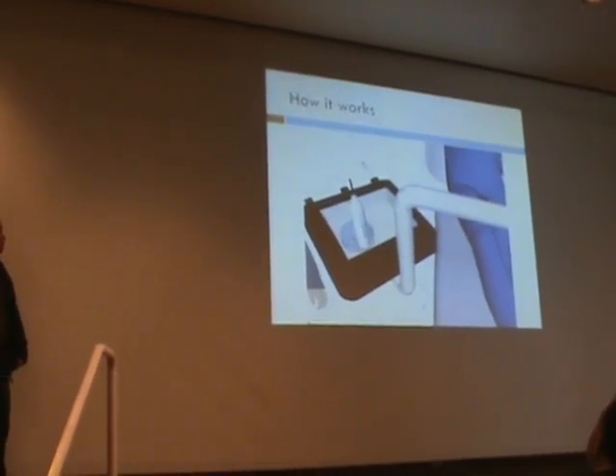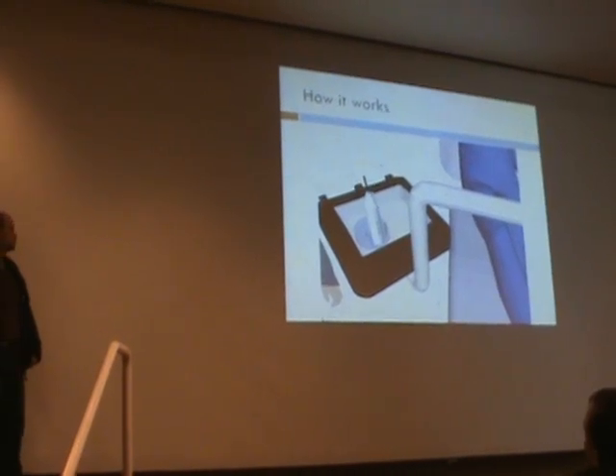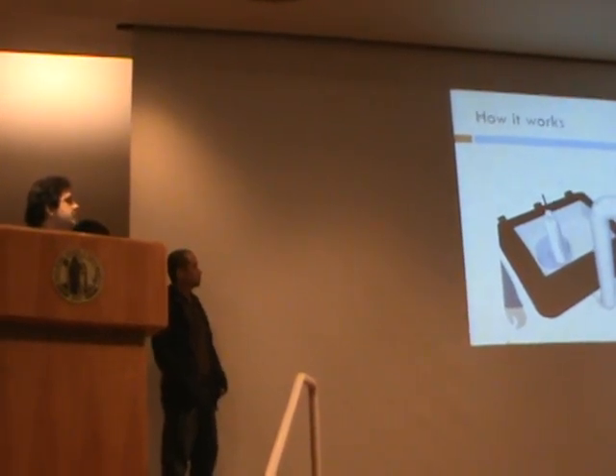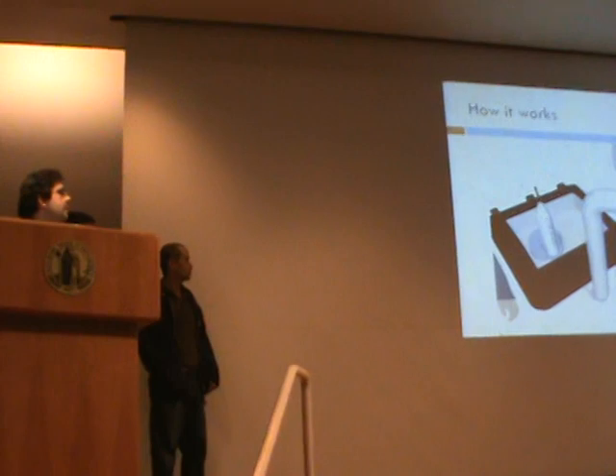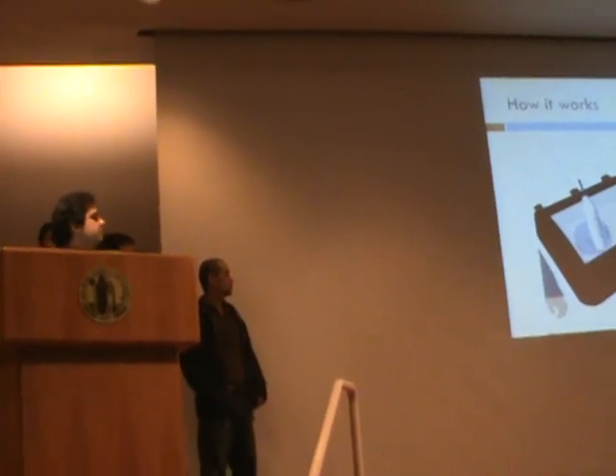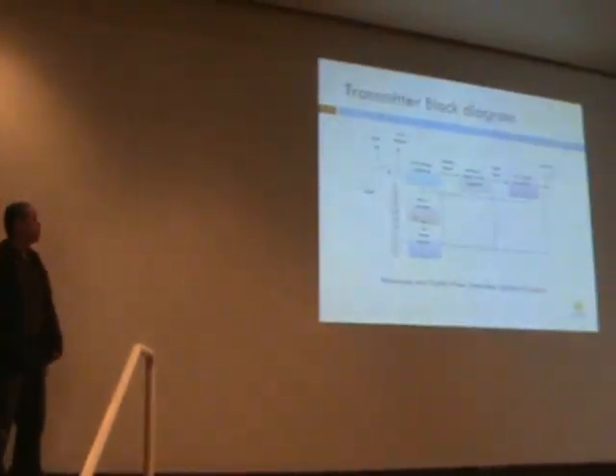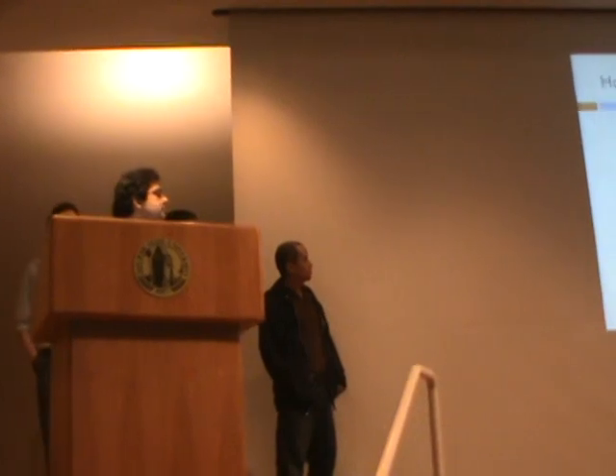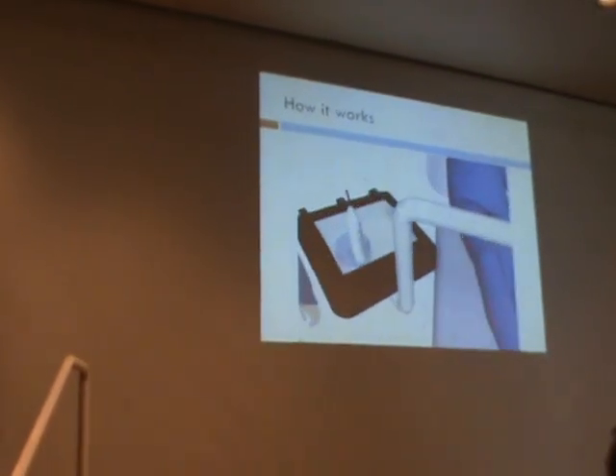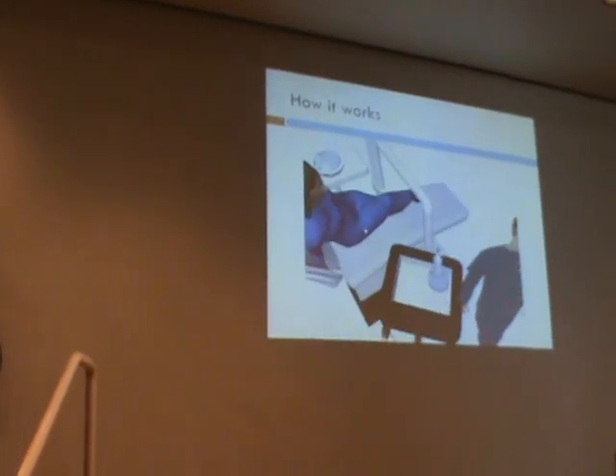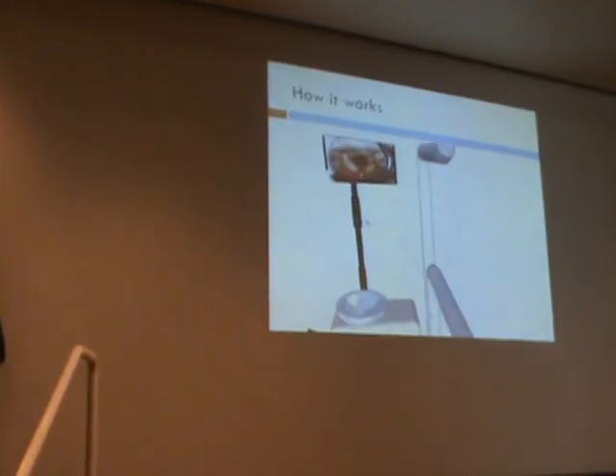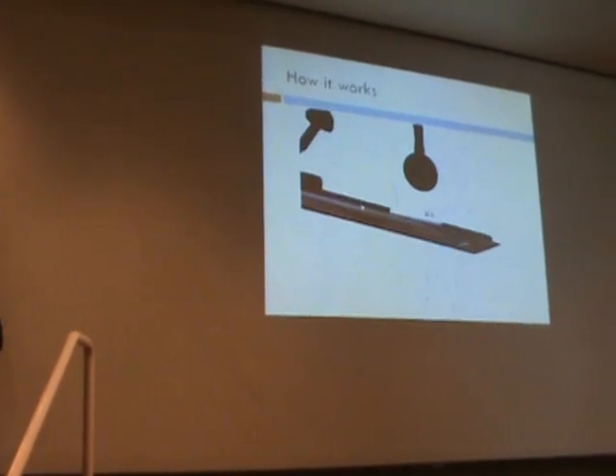This is the handheld video transmitter, wireless transmitter. On the tip of the design, there is a fiber which captures the image and sends it to the CCD located inside the device and wirelessly transmits to the receiver. The receiver is next to the LCD monitor which is located in front of the doctor. This is the actual receiver which has the video output that goes to the TV or any kind of LCD monitor.